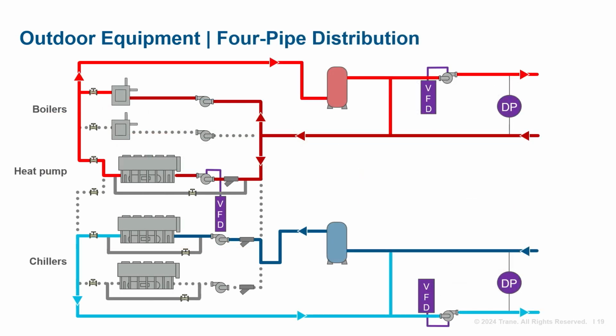This diagram illustrates a four-pipe variable flow distribution served by a packaged heat pump that can produce either hot or cold fluid. Again, the supply equipment sees constant flow, which may vary between heating and cooling, again in a decoupled arrangement. For a cooling dominant load profile, plant efficiency can be further improved with the inclusion of cooling-only chillers.